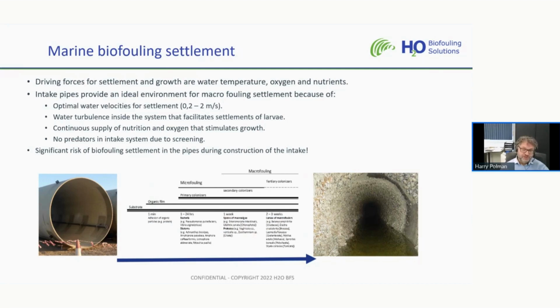During the construction of an intake, there is a significant risk that biofouling settlement will happen during the construction phase. So once the plant starts to commission, the pipes are already fouled and head loss is already present in the seawater system. So special attention during the construction of a seawater intake system is something which we highly recommend, to prevent head loss before the actual commissioning of the utility.